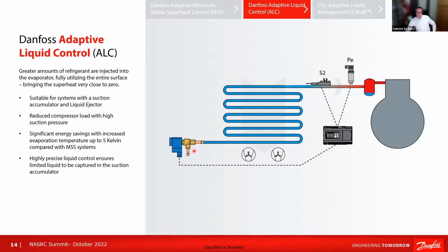This algorithm is very precise and can bring the superheat very close to zero. This allows us to increase the evaporator temperature of the cabinet, working in a semi-flooded condition and achieving a very sustained reduction of energy consumption. It is a highly precise liquid control, and it makes sure that the small amount of liquid that may flow out is captured in the suction accumulator, and then the liquid ejector will take care of it.